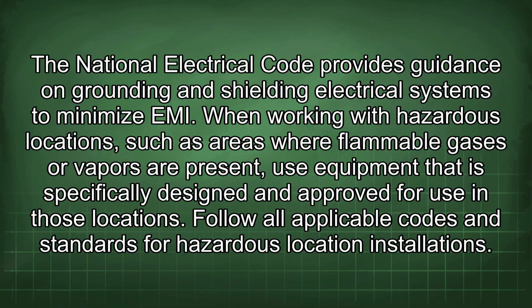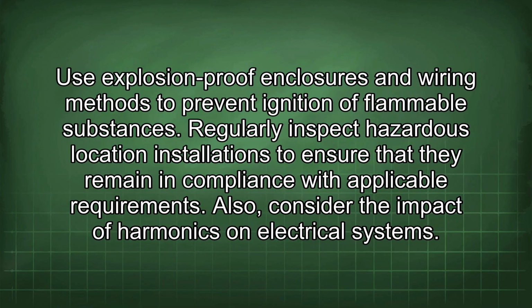When working with hazardous locations, such as areas where flammable gases or vapors are present, use equipment that is specifically designed and approved for use in those locations. Follow all applicable codes and standards for hazardous location installations. Use explosion-proof enclosures and wiring methods to prevent ignition of flammable substances. Regularly inspect hazardous location installations to ensure that they remain in compliance with applicable requirements.